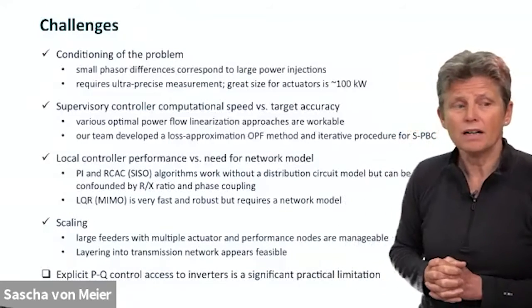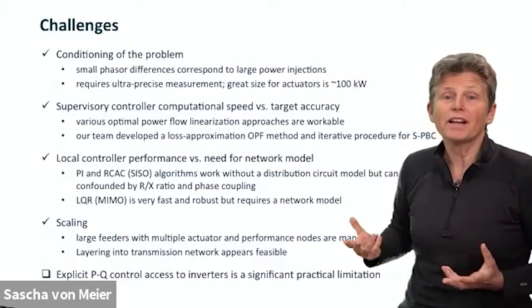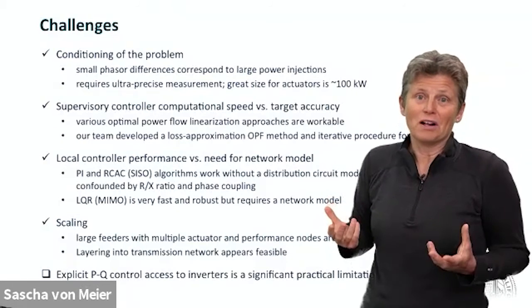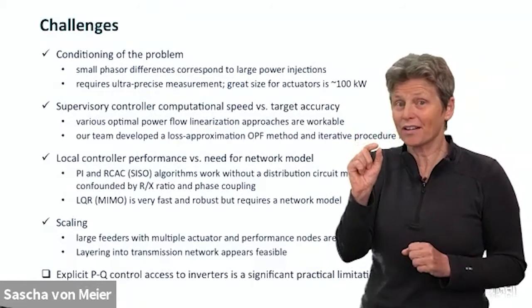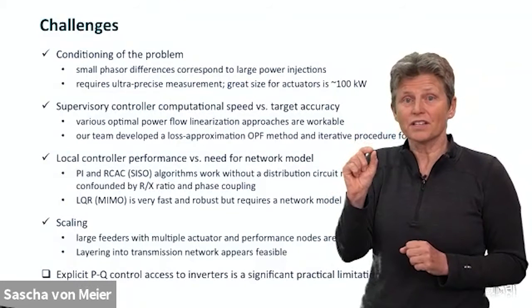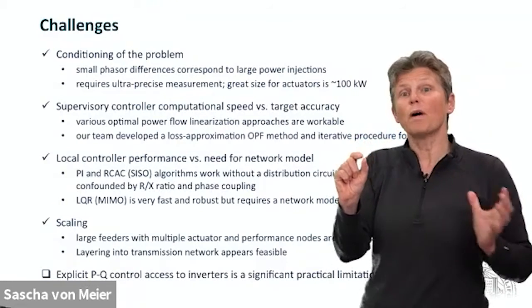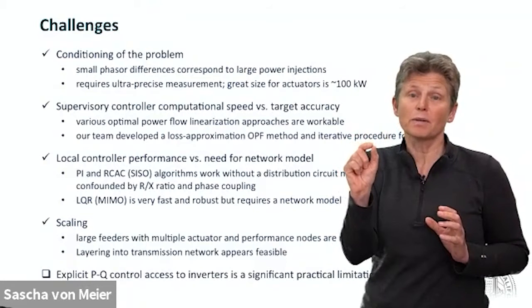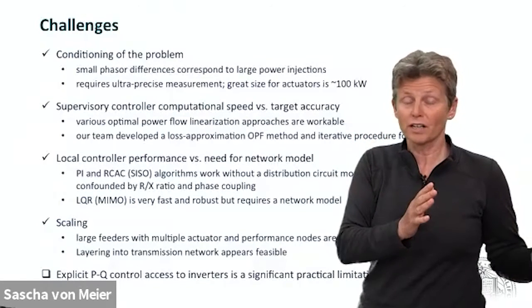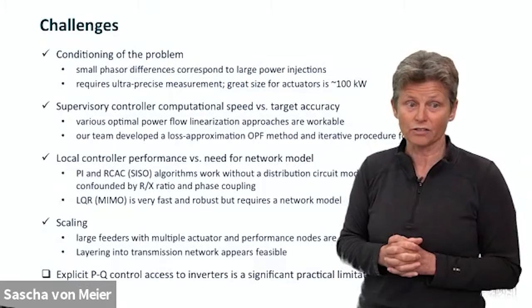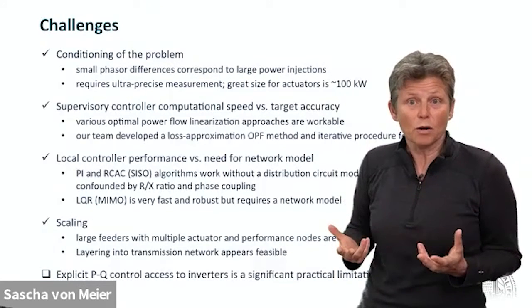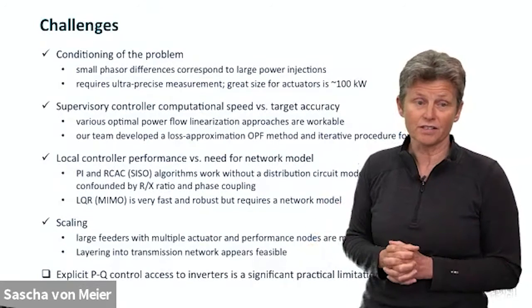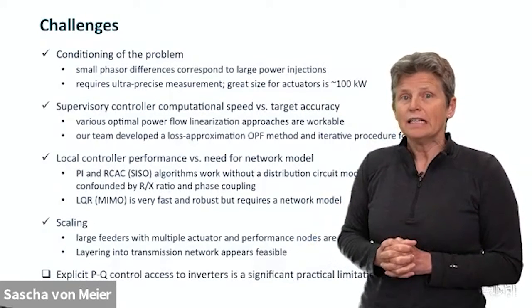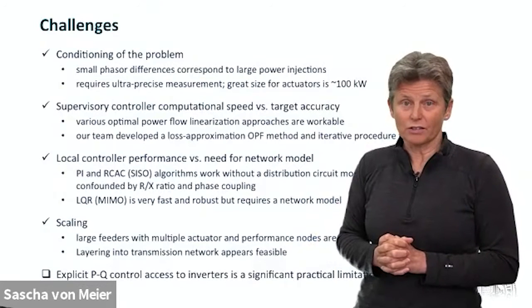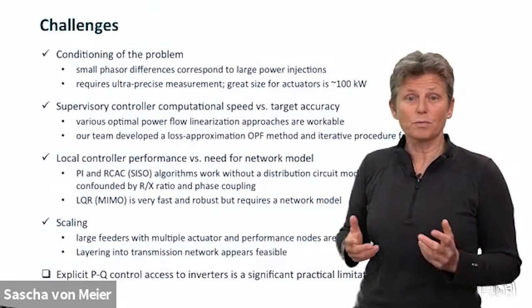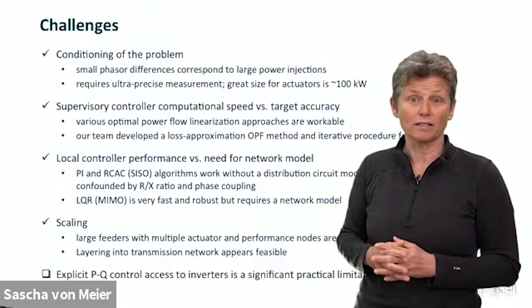So in sum, a fundamental challenge in this problem is that it's just not well conditioned. You're measuring a tiny quantity with tiny differences, and a small error in the phasor measurement corresponds to a large error in the number of kilowatts or kilovars you want to dispatch. But we showed that it is doable under what we think are very realistic assumptions. It's maybe not practical for 10 kilowatt loads, but 100 kilowatts is a great sweet spot for this.